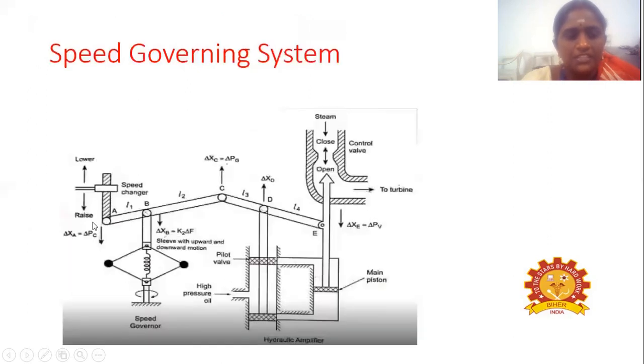For that, if you want to increase the speed, we have to give the increase command to the speed changer. That is, we have to pull the knob in the downward direction. We have to give the raise command. Here, A, B, C and C, D, E are the linkage mechanism and the pivoted points. A pivoted point means it can move either in the upward direction or the downward direction. There will be no horizontal movement; it only allows vertical movement, either upward or downward.